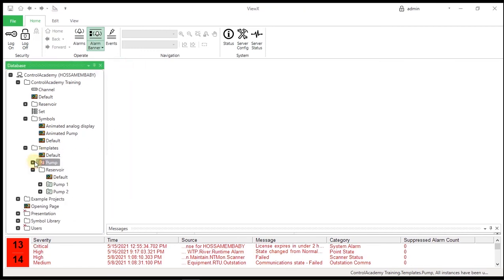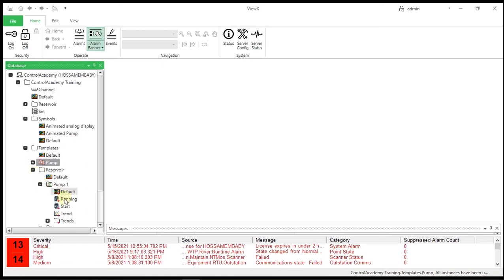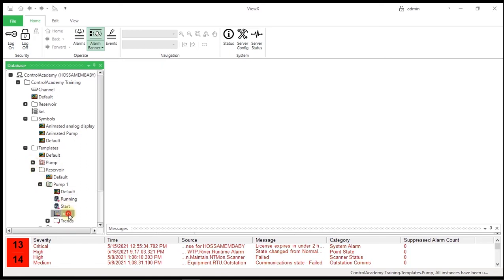Verify that each pump instance has the new trend configured for its running input and that the trace displayed on each trend points to the correct input.